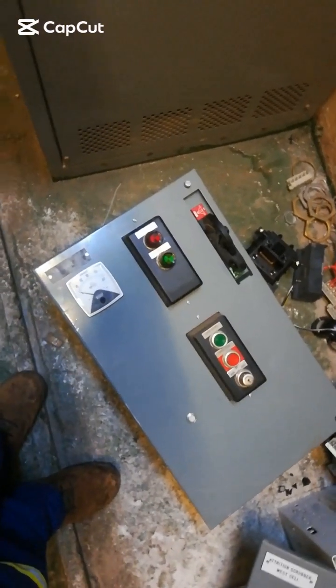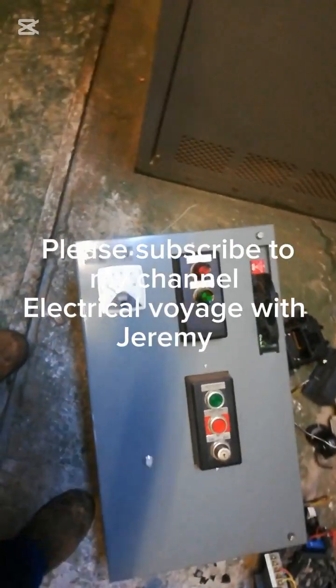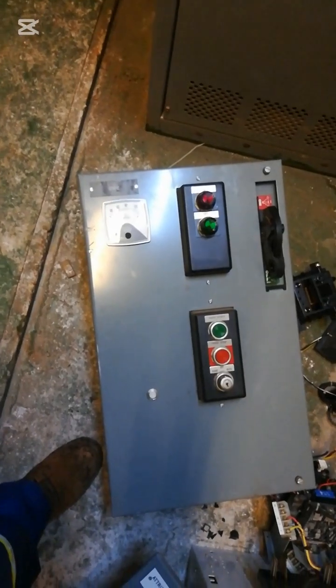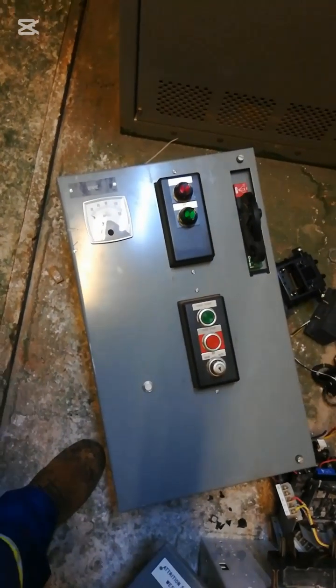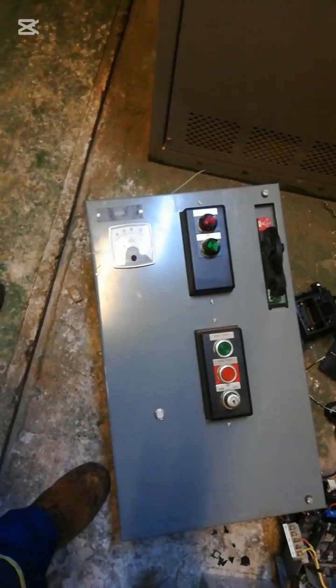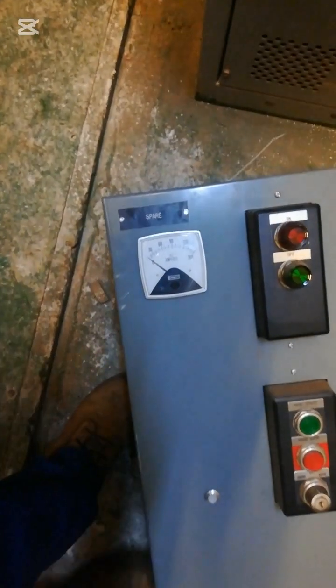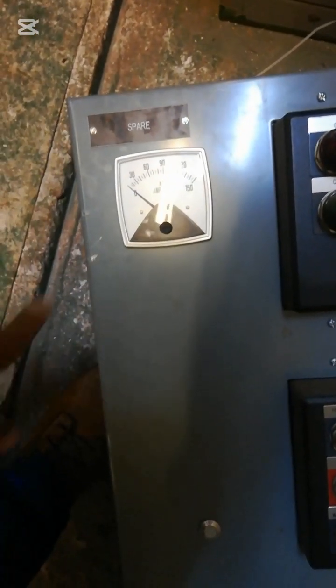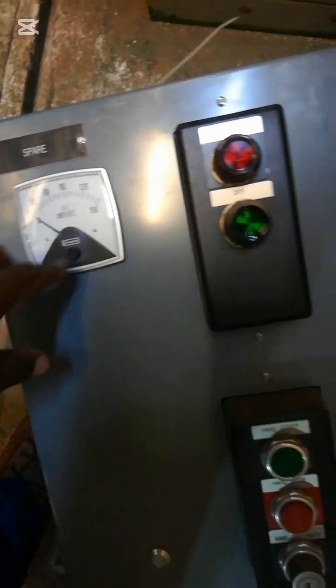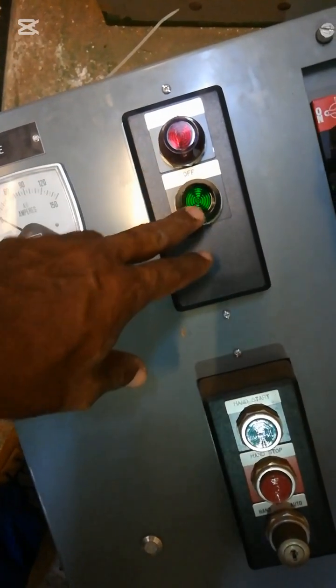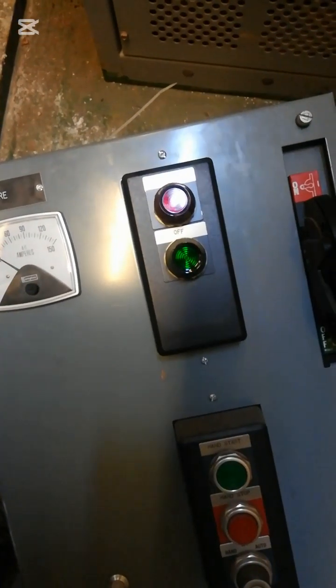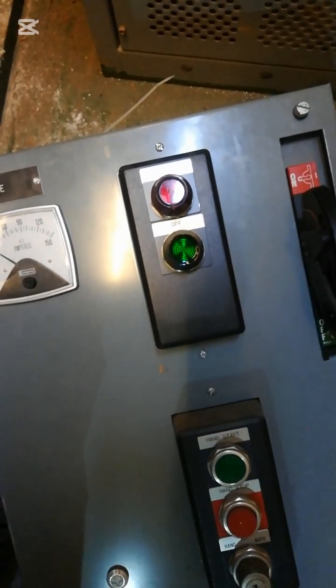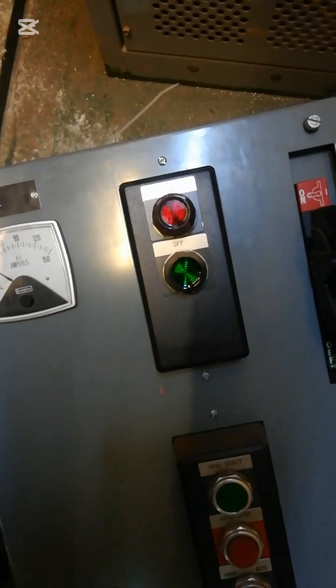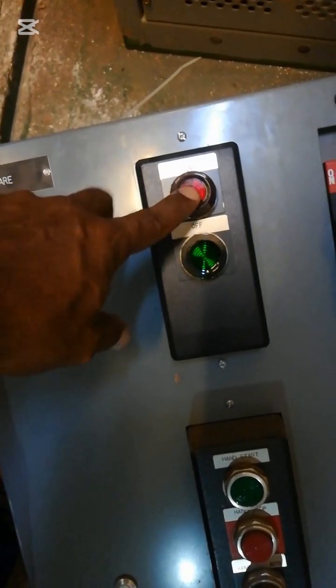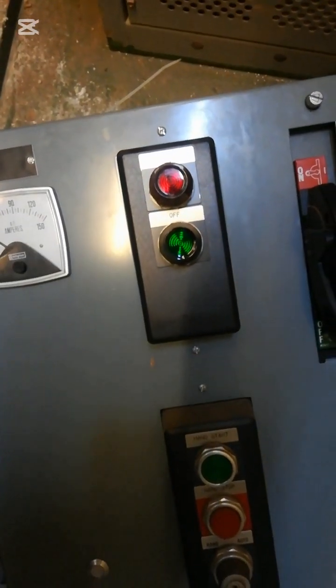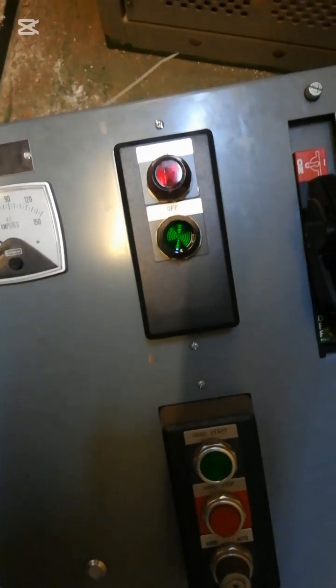What you have here is a starter. This is our electrical panel which starts motors. Electrical motors, right? 3 phase. As you can notice on the panel, you have an ampere meter, an analog, which can tell the amount of current, and you have the button to show start, right, to show the condition of the motor when it is in operation. When it is in operation and it's running, the red light will come on. It's the indicator light. When it is off, you see the green light showing that it is ready to run.